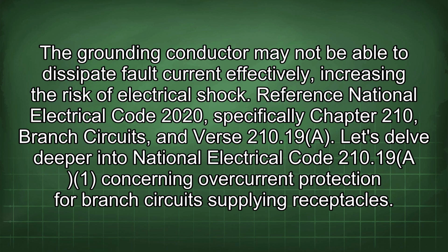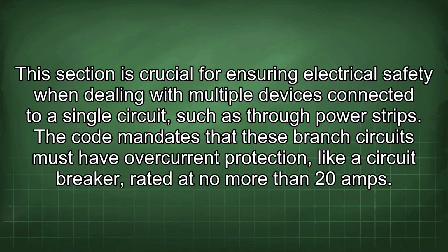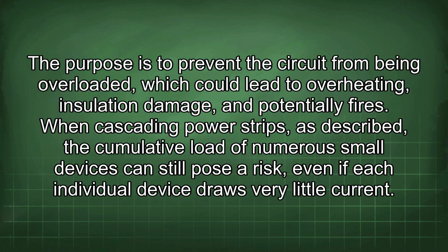Let's delve deeper into National Electrical Code 210.19(A) concerning overcurrent protection for branch circuits supplying receptacles. This section is crucial for ensuring electrical safety when dealing with multiple devices connected to a single circuit, such as through power strips. The code mandates that these branch circuits must have overcurrent protection, like a circuit breaker, rated at no more than 20 amps. The purpose is to prevent the circuit from being overloaded, which could lead to overheating, insulation damage, and potentially fires.